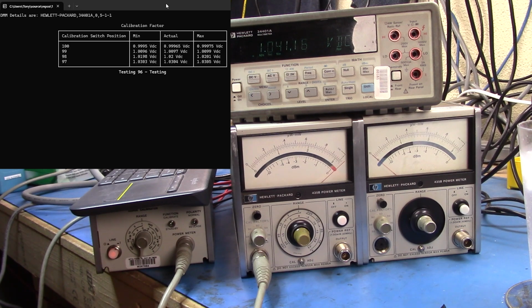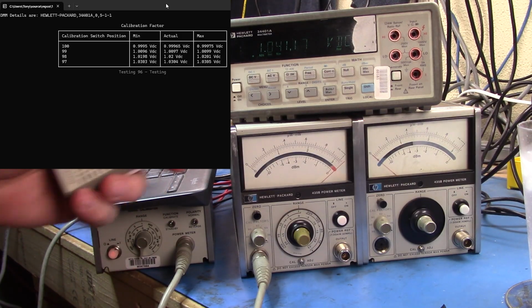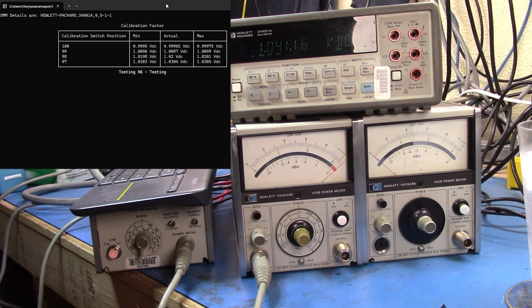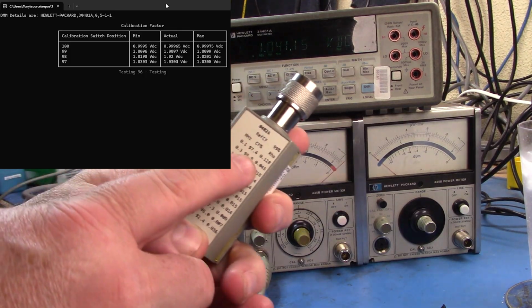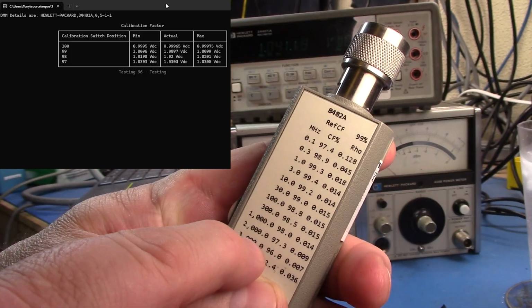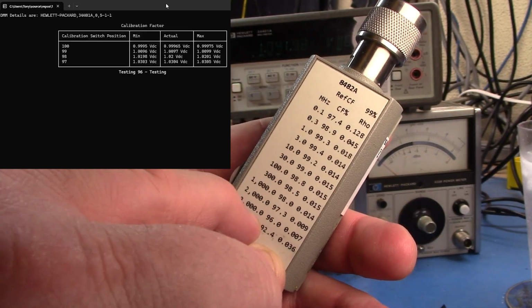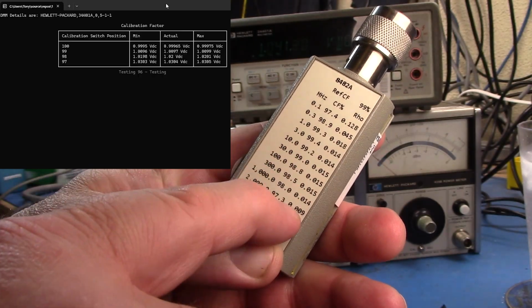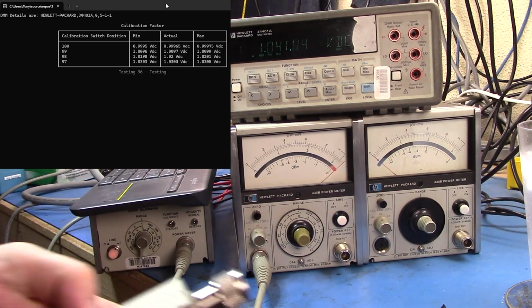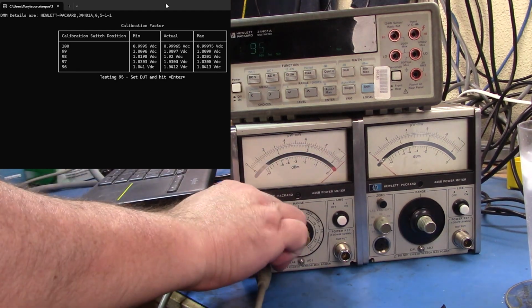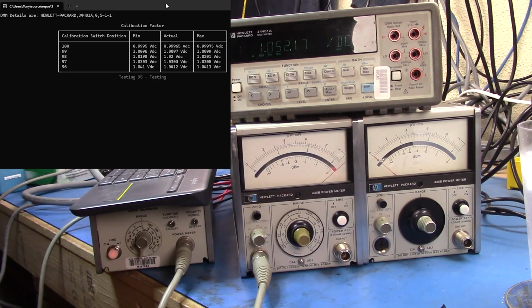I probably should have said this up front. The reason that the calibration knob is here is to normalize the thermocouples across a frequency range. If you have a look at, let me see if I can, we'll see if the camera catches that. But you can see that on this power sensor, there's a set of frequencies, and then there's a calibration factor that gets dialed in to normalize this sensor across that range of frequencies. On the more modern sensors, it's in a piece of non-volatile memory on the actual sensor itself and gets read directly off by the power meter. And it makes it quite good.